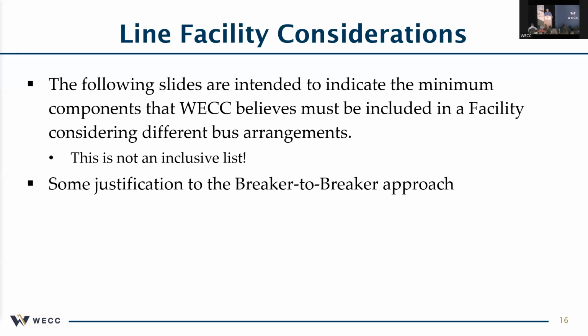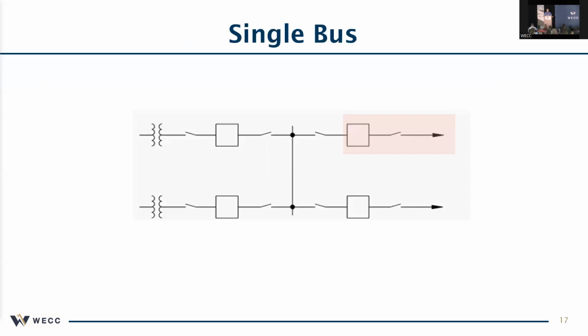So here's the first and the most simple perspective, a single bus. And this shaded area is what WECC would consider that facility, of course, also extending, and it'd be the same picture on the other end. And that would be that line facility, whatever its name may be. Now, realistically, series components, anything on the other side of that line going up to that bus, could also limit that flow. So look how slack we are. We're not even looking all the way back to the bus to that facility. We're going back through the breaker.